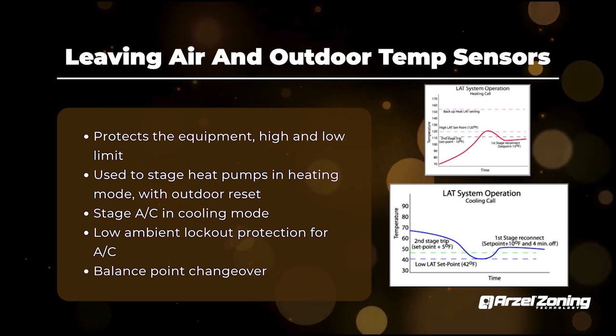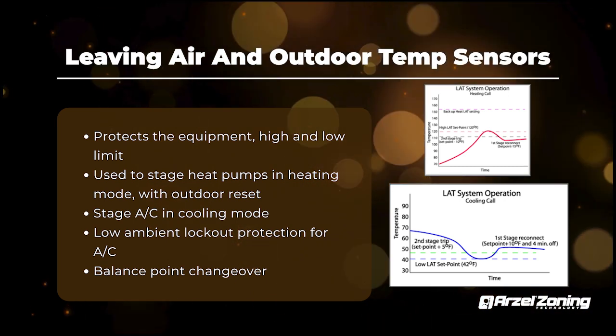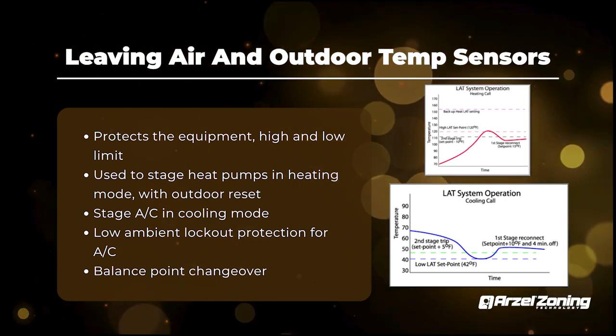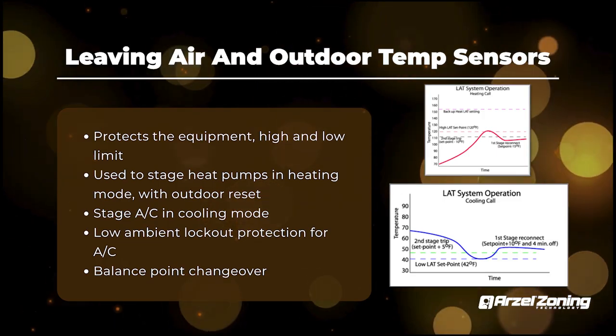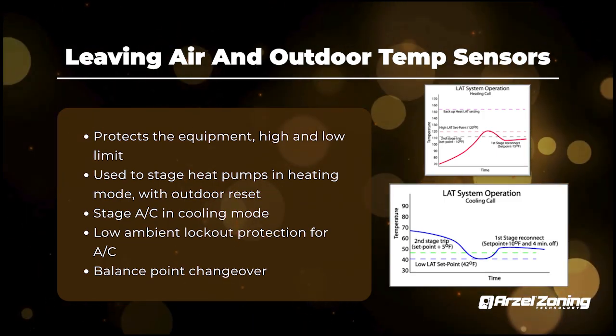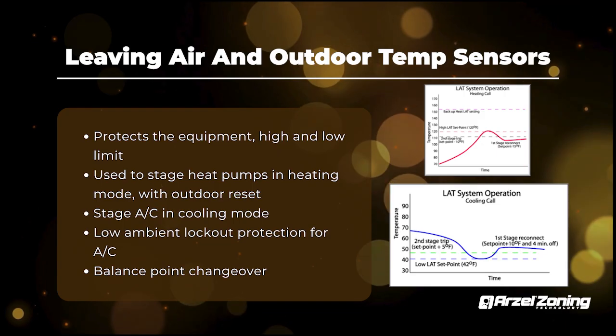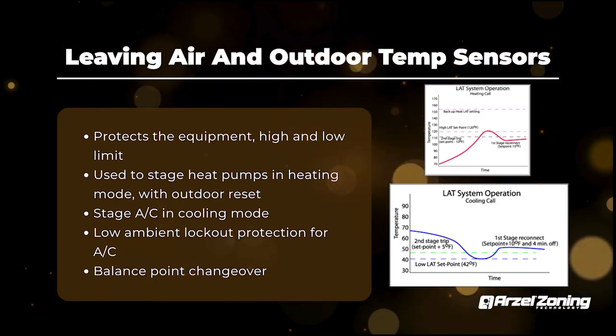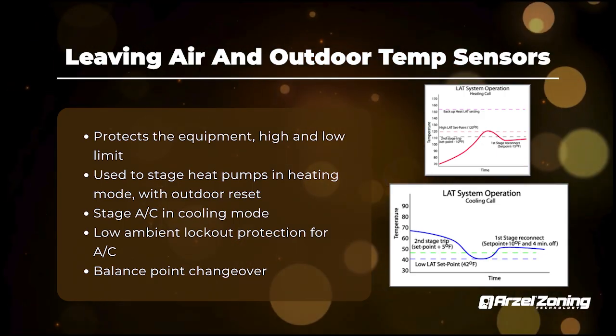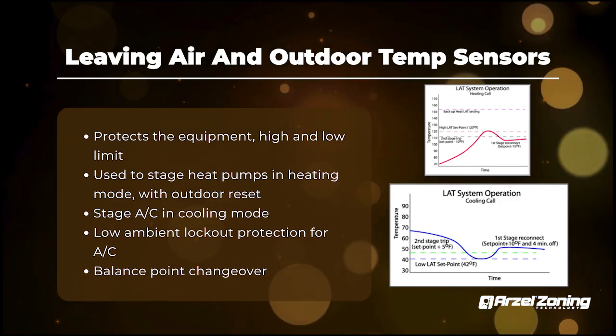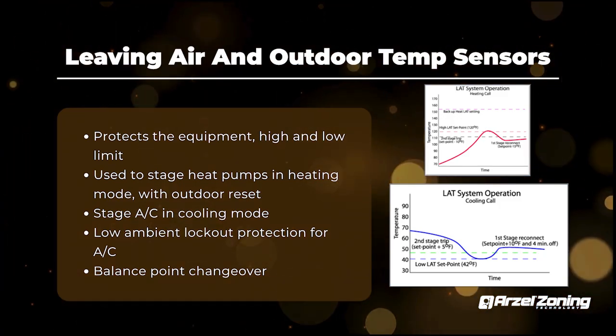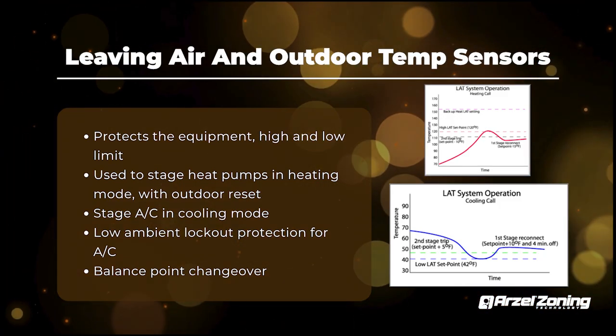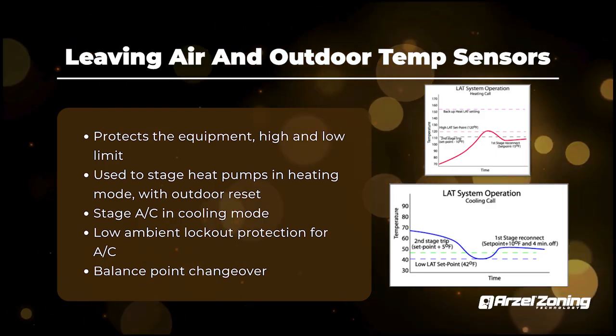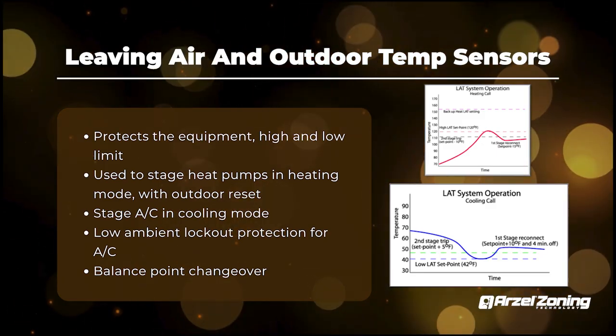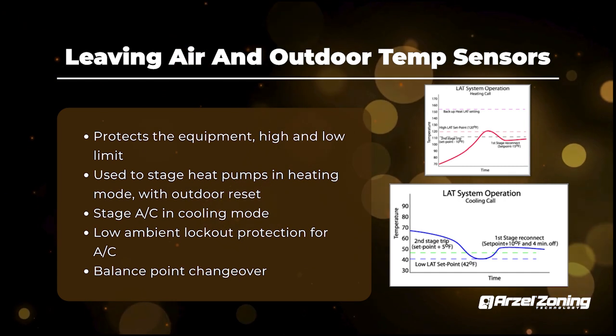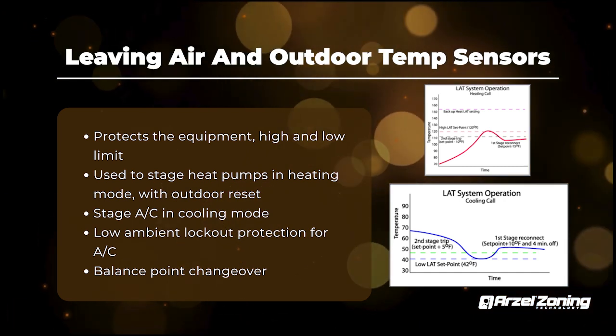So once we get a call for heat, the HeatPumPro is going to engage your first stage of heat, and it's going to start running first stage heat. Then after 3 minutes of runtime, it's going to check ductwork temperature. And if you haven't hit your heat stage threshold setting yet, it's going to upstage that equipment to second stage. It'll run for another 3 minutes, read that temperature again. If it still hasn't hit the heat stage threshold setting, then it would engage your auxiliary heat or your backup heat source. So that's really how the staging works. It does it based on leaving air ductwork temperature.